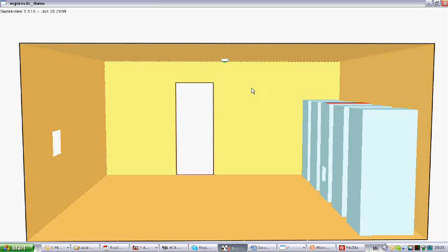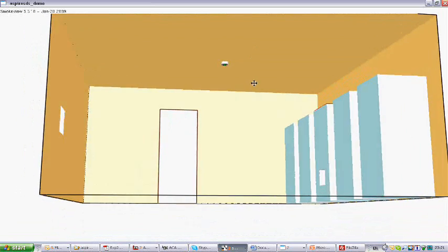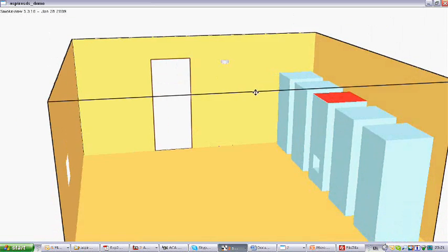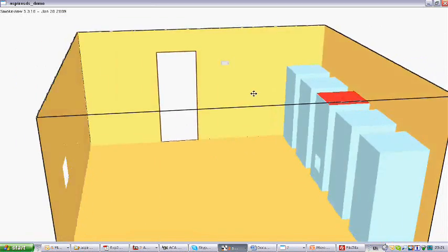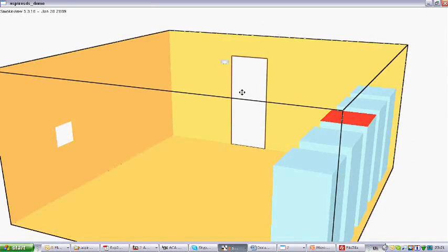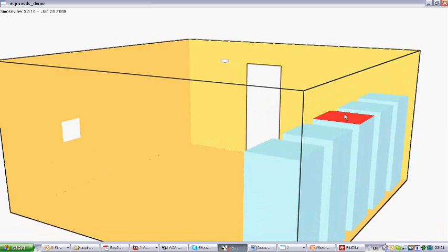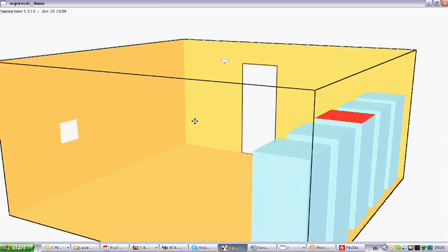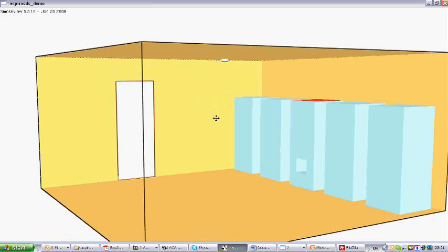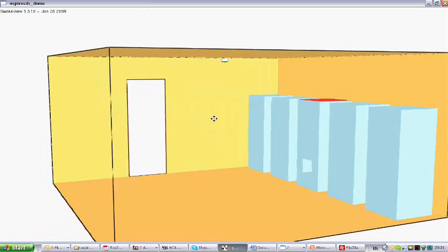We're actually looking at a 3-dimensional model which can be viewed from any angle using the Smokeview software which accompanies FDS. What we have done is we've simulated a fire, a small 2.3 kilowatt fire in the middle cabinet, and we can visualize the results of that fire by turning on a couple of slices within the space to reveal the smoke density predicted in a couple of planes.